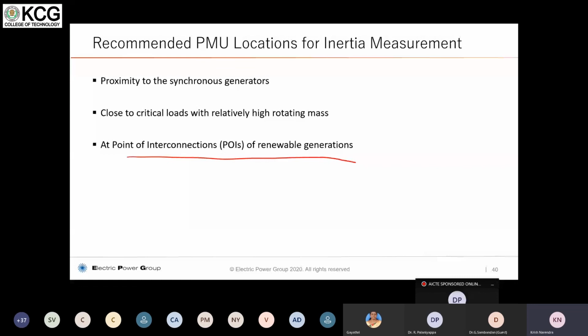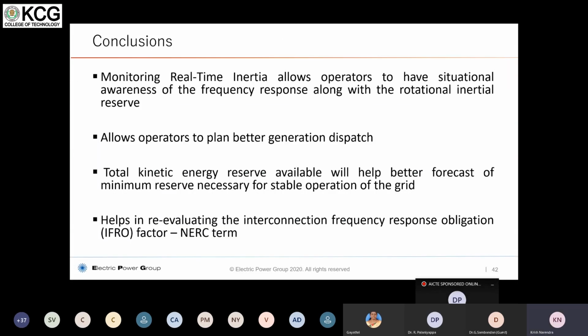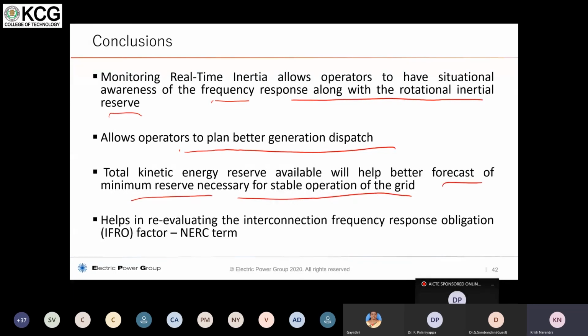In conclusion, monitoring real-time inertia allows operators to have situational awareness of the frequency response and the rotational kinetic energy reserves. It allows operators to plan better generation dispatch. The total kinetic energy reserve available will help give a better forecast of the minimum reserve necessary for stable operation of the grid. And it helps in re-evaluating the interconnection frequency response obligation. This may be with respect to NERC in North America, but it is equally applicable to India, depending on the index they are utilizing.